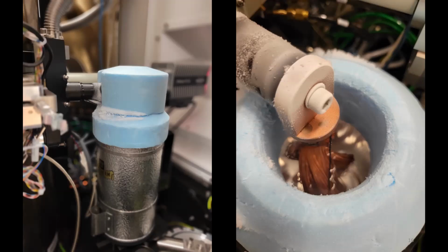So to protect it, we have this cold finger. And so you can see this copper braid, and there's a copper rod that goes inside, and then there's this little shroud that goes around where your sample comes out. And so anything that off-gasses, most of the time, is going to condense on that cold finger. And then what we do is every night when we get done, we put it in what's called a cryocycle, where it runs the turbomolecular pump for 10 hours and lets that cold finger heat up so that it sucks all of the moisture out of there. And at that time, the ion gettering pump is turned off to protect it from the moisture itself.